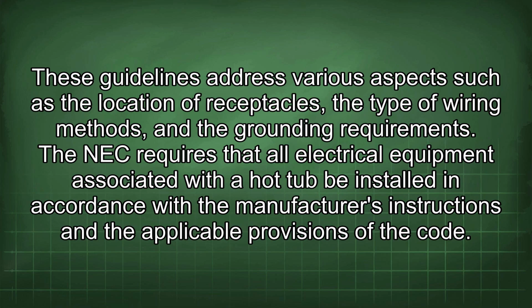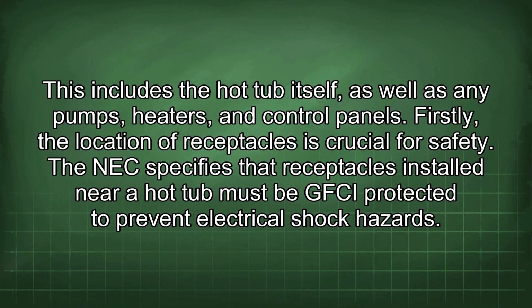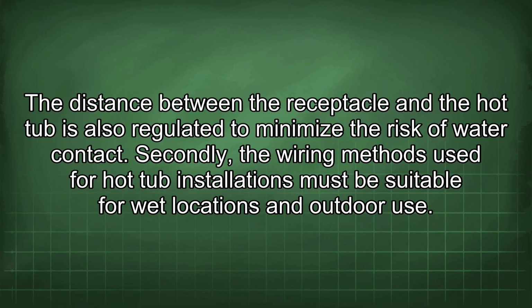These guidelines address various aspects such as the location of receptacles, the type of wiring methods, and the grounding requirements. The NEC requires that all electrical equipment associated with the hot tub be installed in accordance with the manufacturer's instructions and the applicable provisions of the code. This includes the hot tub itself, as well as any pumps, heaters, and control panels. Firstly, the location of receptacles is crucial for safety. The NEC specifies that receptacles installed near a hot tub must be GFCI protected to prevent electrical shock hazards. The distance between the receptacle and the hot tub is also regulated to minimize the risk of water contact.